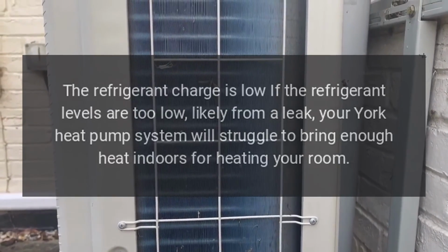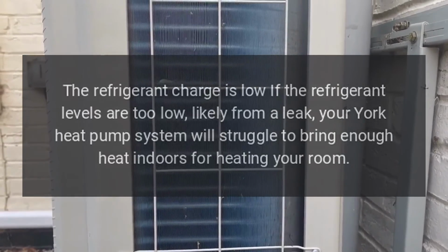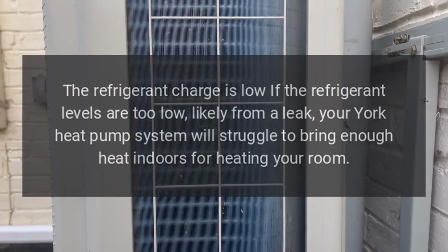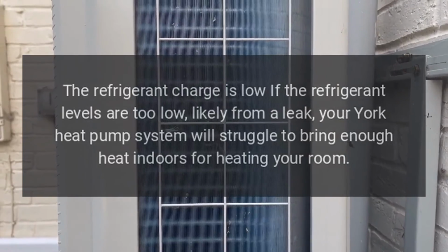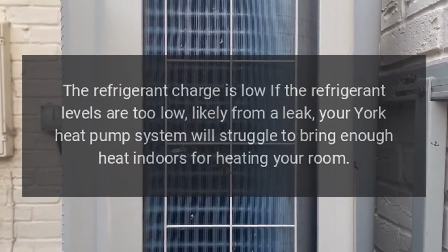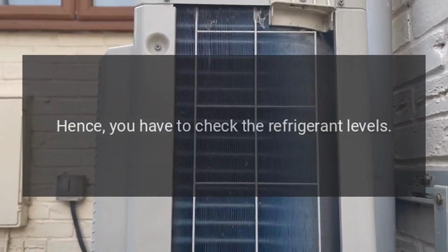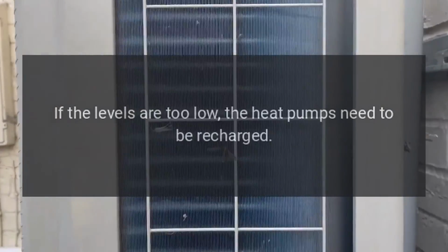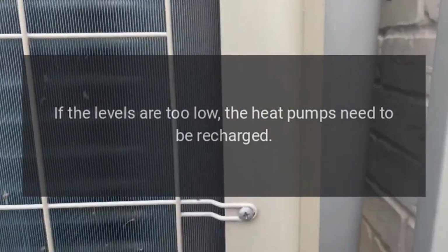The refrigerant charge is low. If the refrigerant levels are too low, likely from a leak, your York heat pump system will struggle to bring enough heat indoors for heating your room. Hence, you have to check the refrigerant levels. If the levels are too low, the heat pump needs to be recharged.